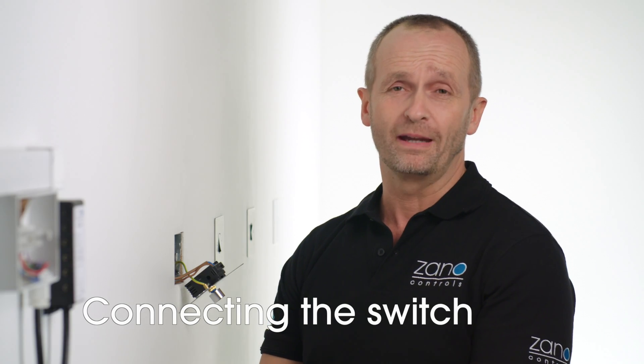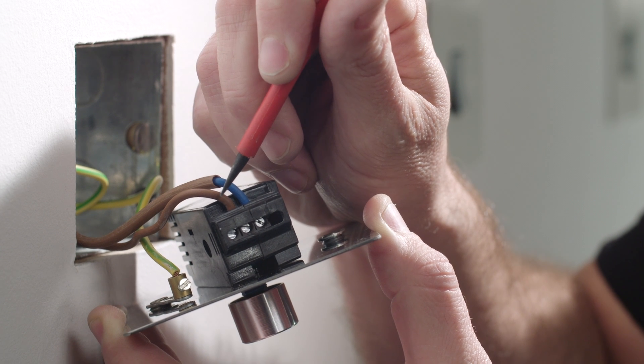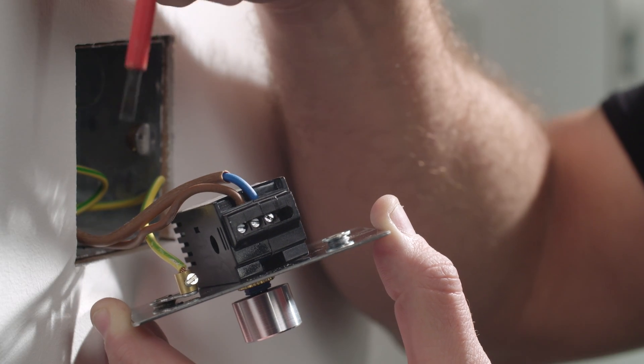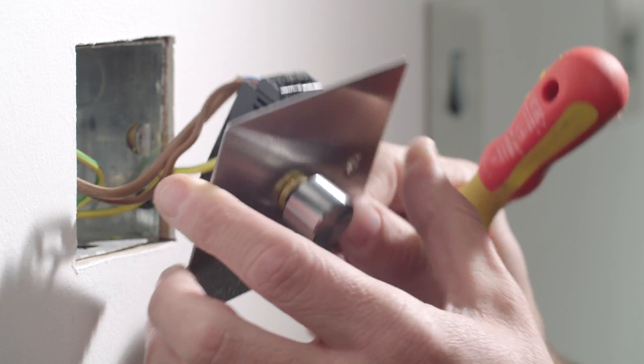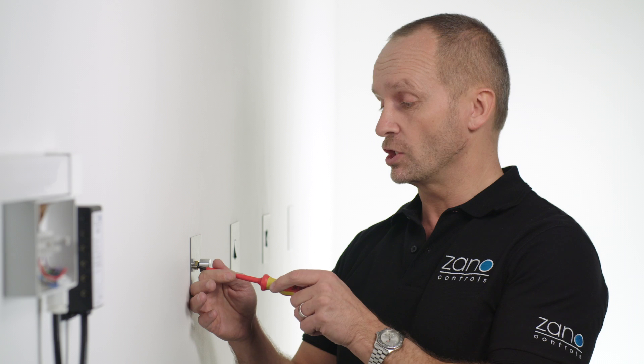Now let's connect the switch. You can use grid module or plate mounted. Zano rotary controllers are all wired the same way. Take the brown wire L1 and connect to the terminal labeled six. The blue wire connects to terminal seven. Also be absolutely sure to terminate your earth cable according to regulations. Now fix your switch back to the wall or switch box securely and safely, ensuring all terminations are safe.